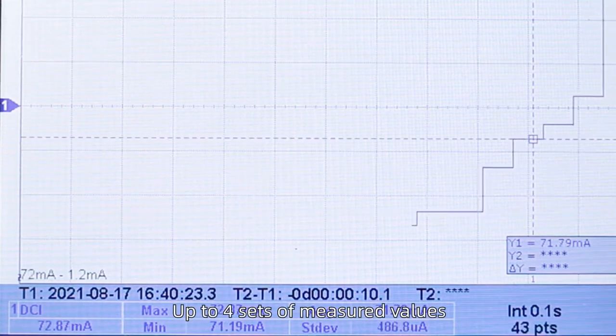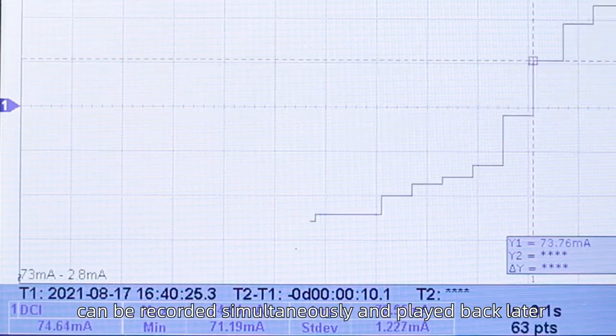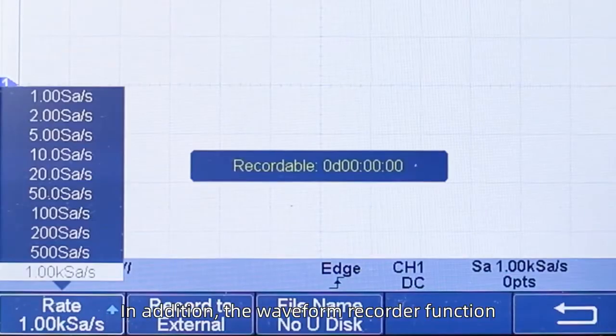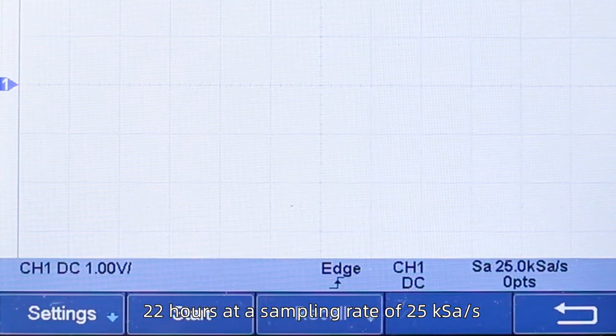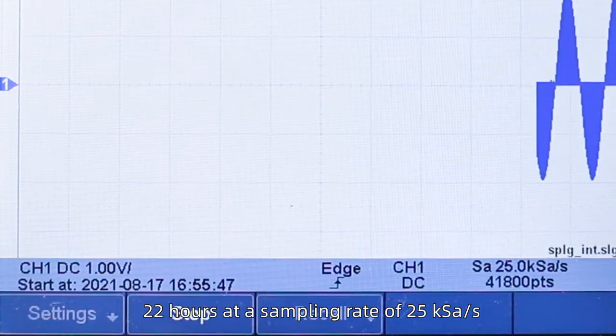Up to four sets of measured values can be recorded simultaneously and played back later. In addition, the waveform recorder function can continuously record waveforms for up to 22 hours at a sampling rate of 25 kSa per second.